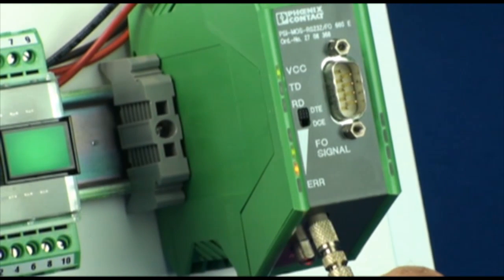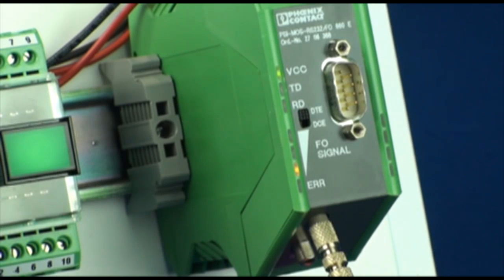When the signal reaches the 10% power reserve setpoint, the yellow LED will illuminate and a remote relay contact will switch.